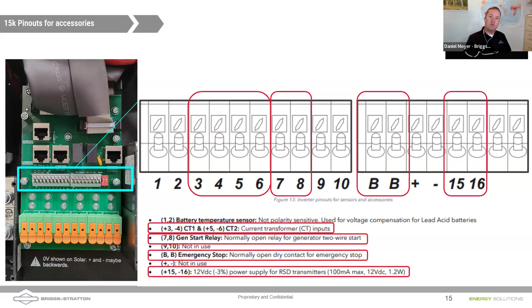Now, I know that Tigo, if you look carefully on some of the Tigo transmitters, we've got to power a transmitter, which then sends a signal along the PV cables to the rapid shutdown devices, the TS4Fs up on the roof. That transmitter sometimes requires more than 100 milliamps. I've heard that the new Sol-Ark 12K is going to be more powerful, so we no longer have to put in that breaker with the power supply. Can you shed any light on that?